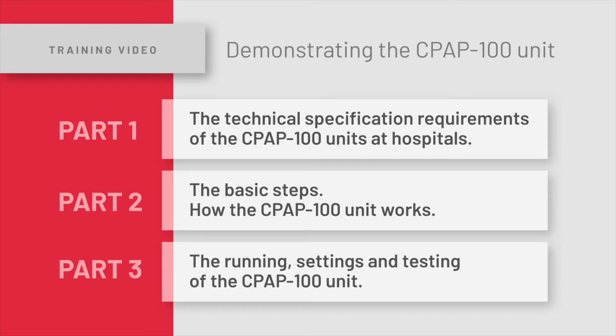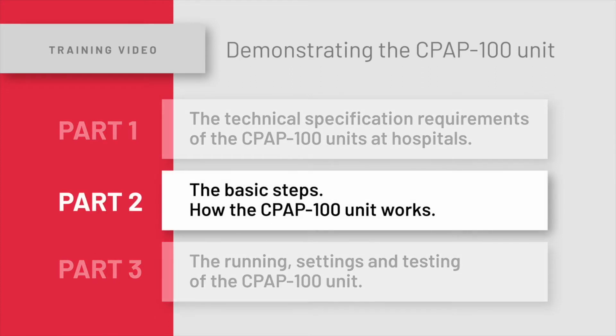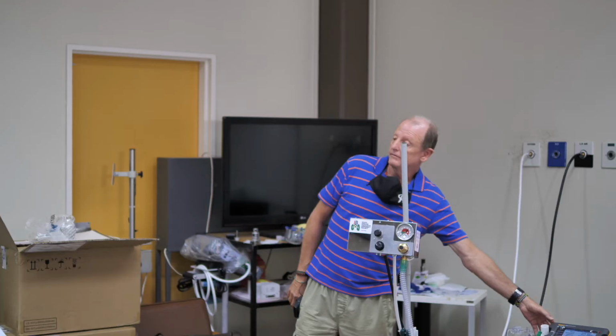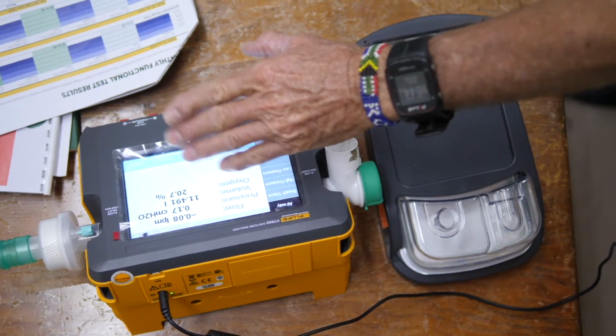It's a very simple thing. I know you guys are highly qualified as clinical engineers, but it's a simple test that has to be done. What you do need is a Fluke analyzer or a ventilator analyzer that can do flow and percentage. Don't worry about the volume of flow. All you want is the flow rate and a percentage that you can read, and a pressure.